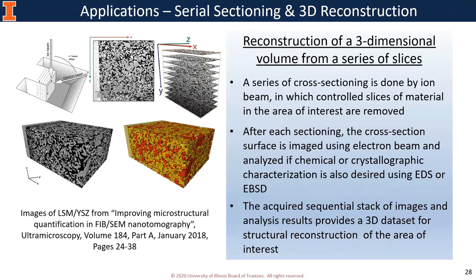There is also 3D serial sectioning and 3D reconstruction, also called 3D tomography. A series of cross-sections is done by the ion beam, in which controlled slices of material in the area of interest are removed. After each cross-section, the surface is imaged using the electron beam and analyzed for chemical or crystallographic information if the right detectors are available. The acquired sequential stack of images and analysis results provides a 3D dataset for structural reconstruction.